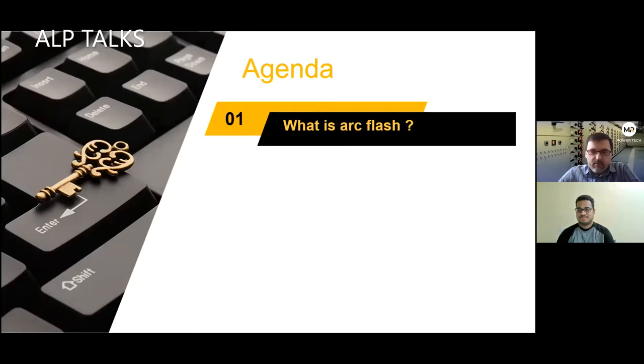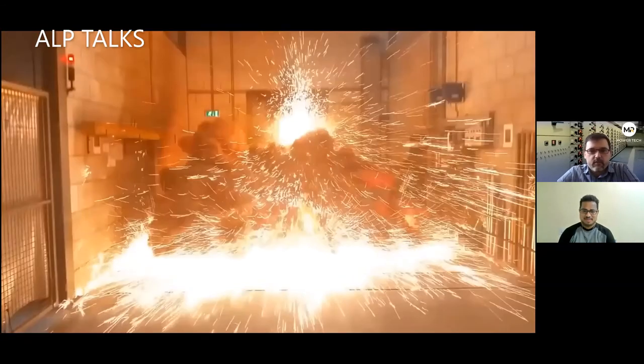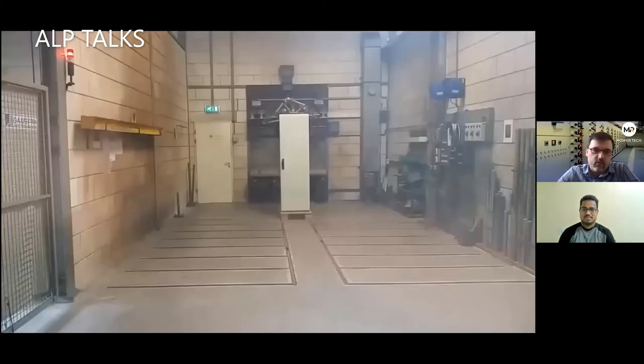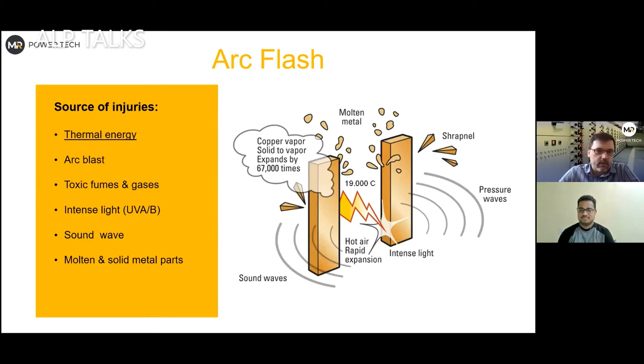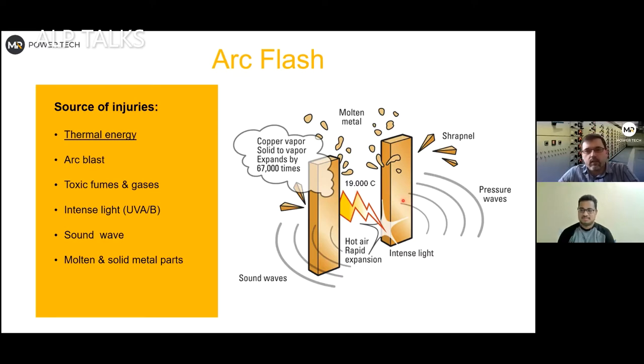The main question is: what is arc flash? I prefer to show it rather than describe it. I'll show a video from Tesla — just to keep it short. What you saw was temperatures between 5,000 to 19,000 degrees — that's the thermal effect. Ionized gas creates a path for the arc to travel between electrodes. Those two electrodes can be anything — bus bars, cables, metallic parts, or even a person.